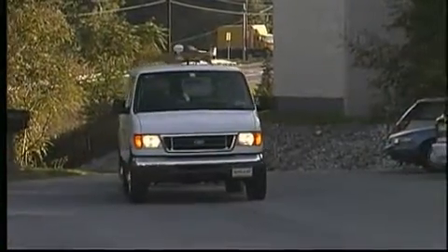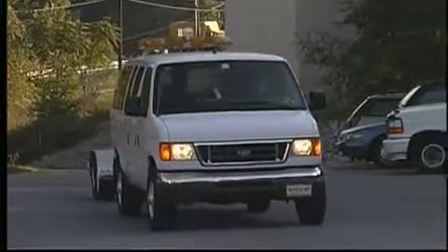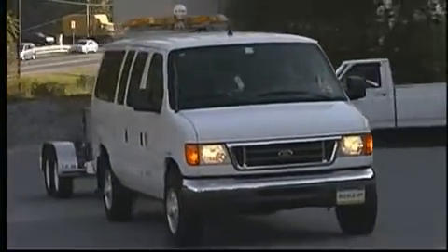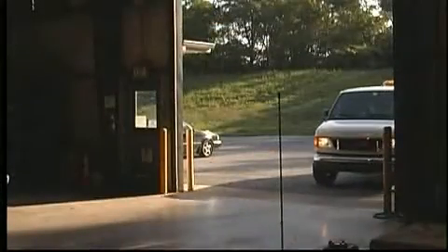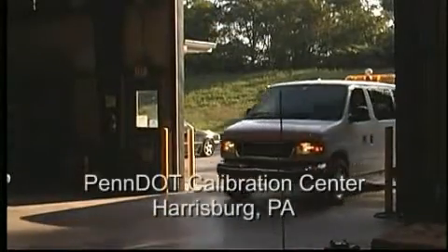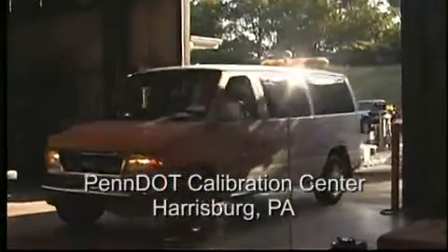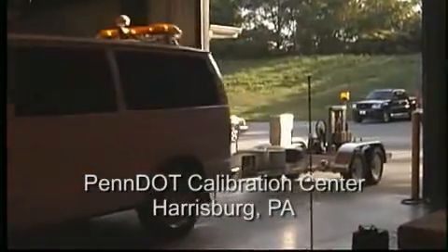If possible, drive to the center the night before the scheduled calibration. Once on site, get the FWD ready and warm it up. This is typically done outside, but sometimes it has to be done inside. Then drive into the calibration center facility and maneuver the FWD into position.